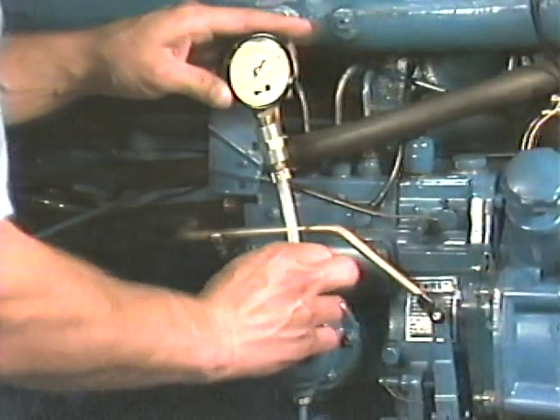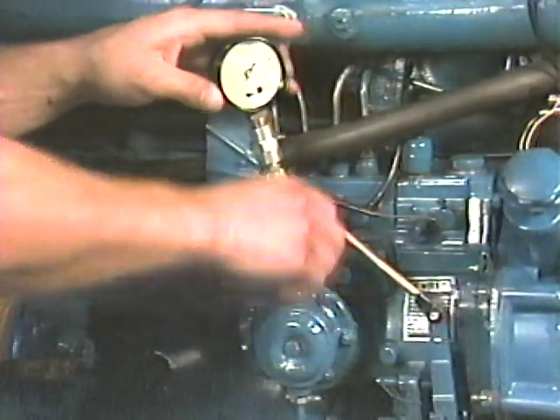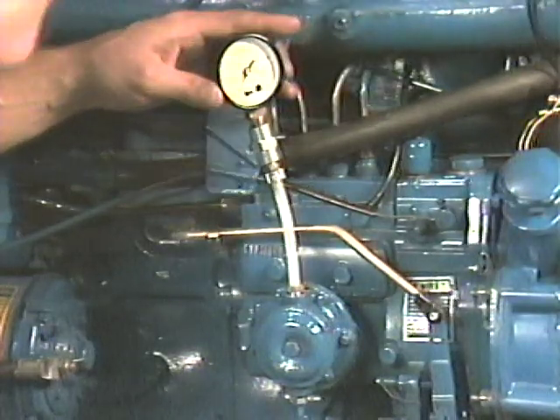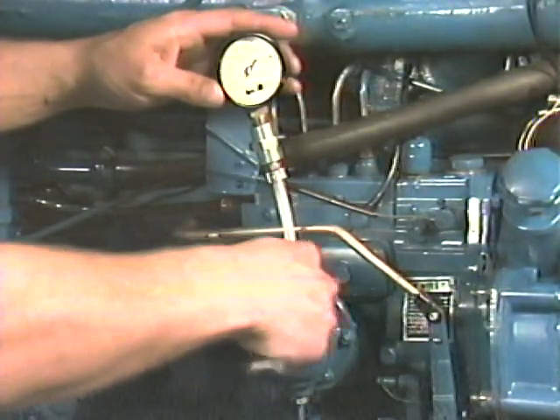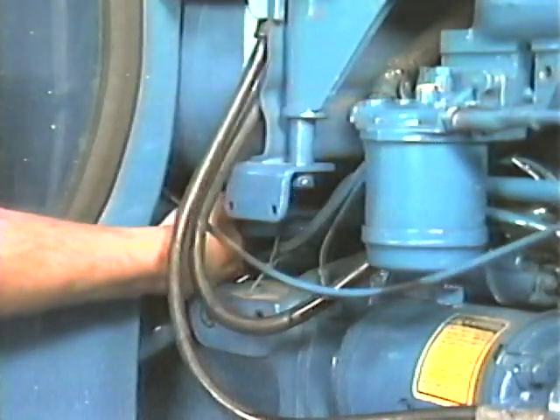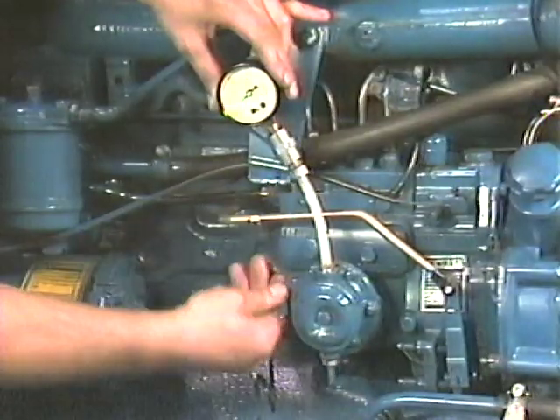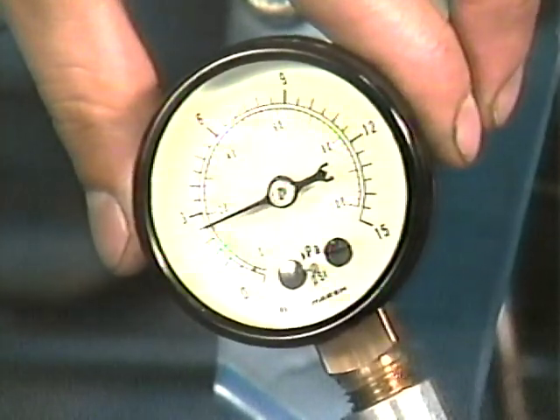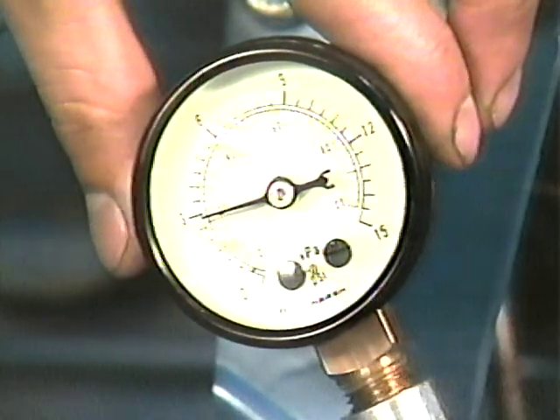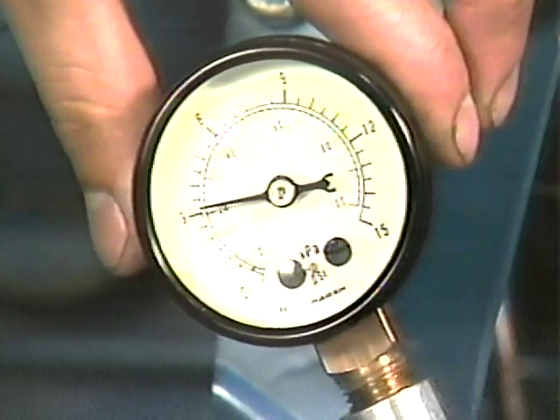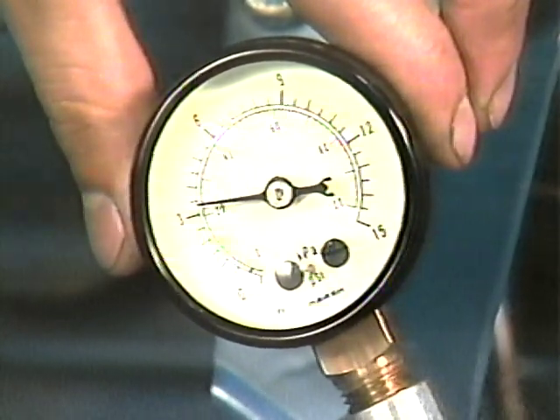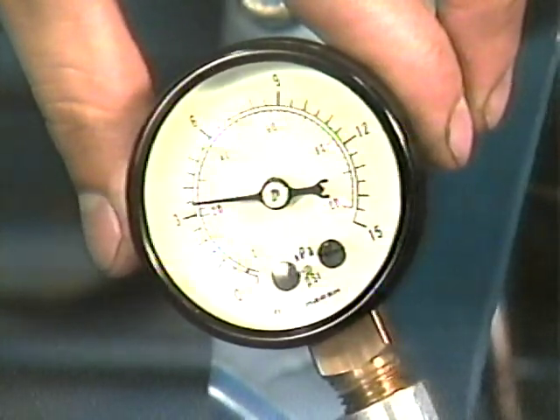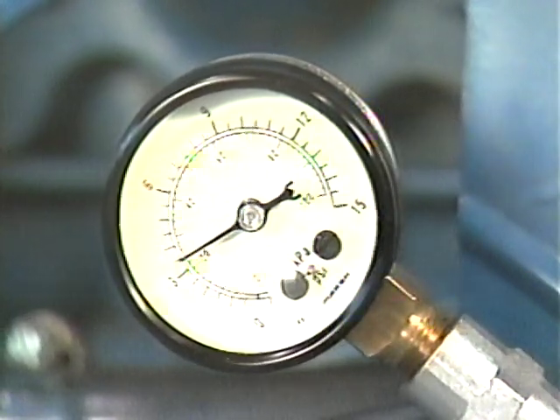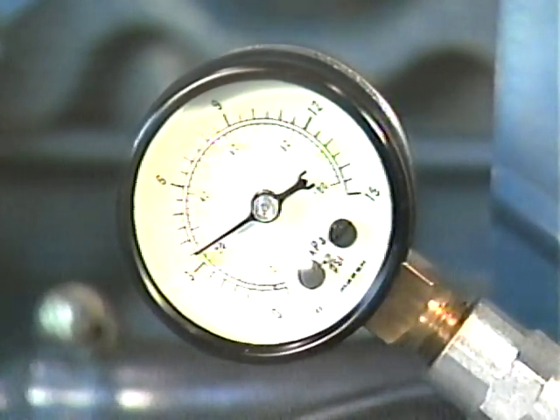When the cover is reinstalled, connect the pressure gauge and tube assembly at the fuel pressure line on top of the lift pump. Turn on the fuel tank valve again and pump up the lift pump until the pointer on the gauge rises to its maximum level. Observe the gauge reading. Pressure should be a minimum of 2.5 pounds per square inch. It should hold at that pressure for 5 minutes. If it doesn't, install a new lift pump.